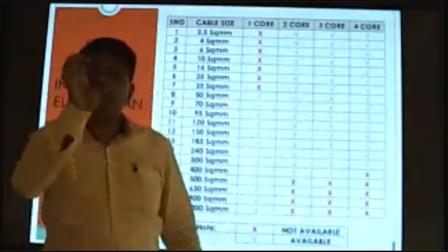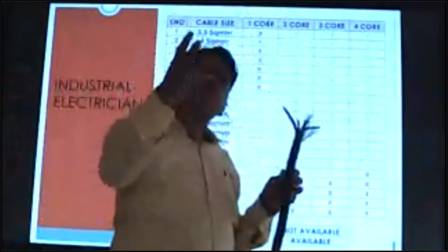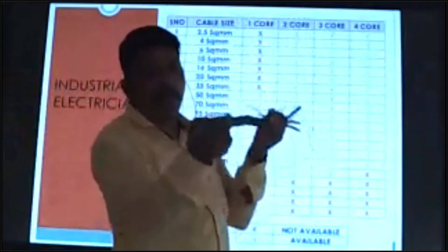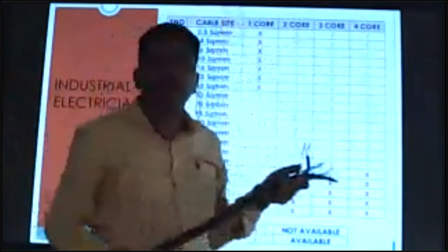Important for you: at glanding time, you should check the sizes of the cable. All cable sizes are written on the outside of the insulation, like 1 core 4 mm square or 2 core 10 mm square. You can check there; no need to measure with a tape. The outside already has the marking, 1 core, 2 core, 3 core, or 4 core. Not inside, only the outside writing somewhere. Check the writing place and you can find it. Yes, clear.